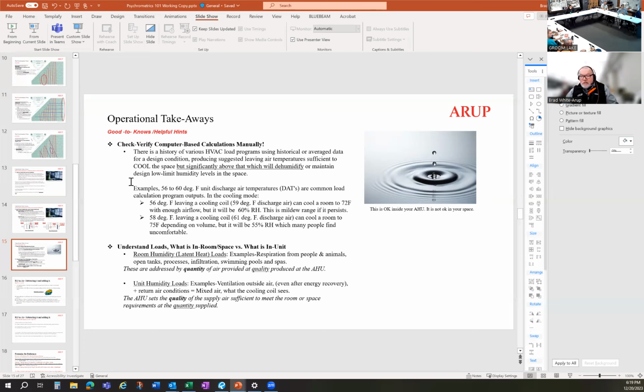You know, VRF systems, I think you're all familiar with those. They don't dehumidify worth a darn. They will dehumidify by accident or on occasion, but they're not going to be targeting humidity without extensive controls. They're not really made to do that. They just want to take the temperature down, but they tend not to remove humidity unless it's already muggy in the space. So that's why I want to get that air down, again, below 55, 50 if I can.